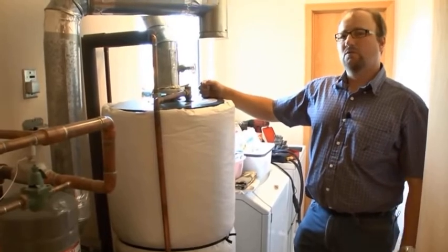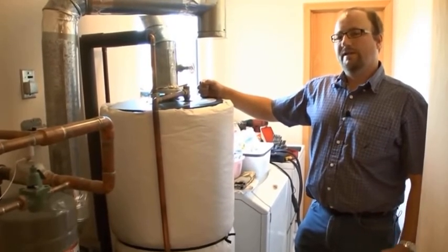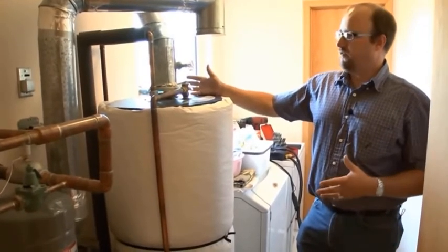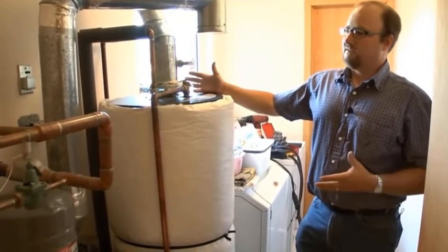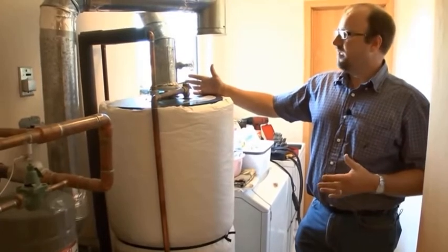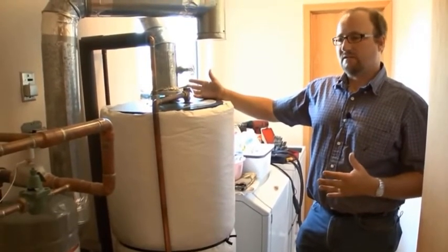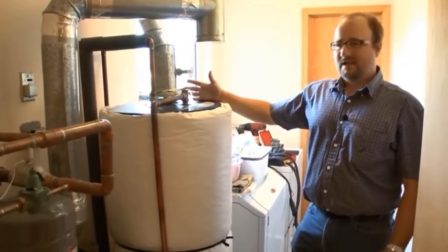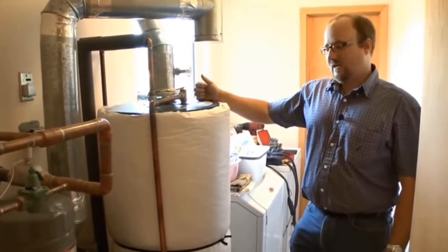So in order to move forward, we have to turn off the fans, open the doors, and see if we have draft under the best of conditions. If we do have draft under the best of conditions, then we can continue. If we don't have draft, then we cannot continue with our diagnostics.